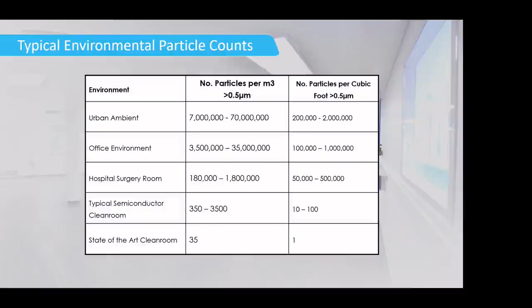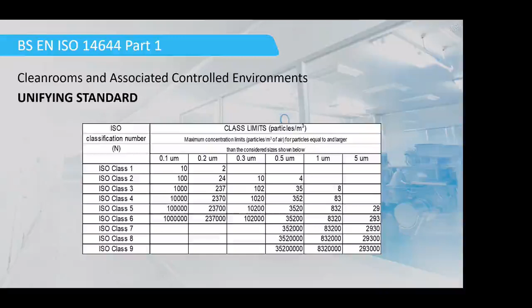So I talked earlier about classification. What you'll do is classify usually at 2 particle sizes, 0.5 and 5 microns. You use a device called a particle counter to count the number of particles in the air, and then you can see the classification on the left-hand side there. Usually that's defined up front, so you'll know from your process or the medicine you're producing what classification you need, and then design for that using prior experience to define things like filter grade, amount of air, and number of times we change out the air every hour within a space, which will then define how clean we can get the room.